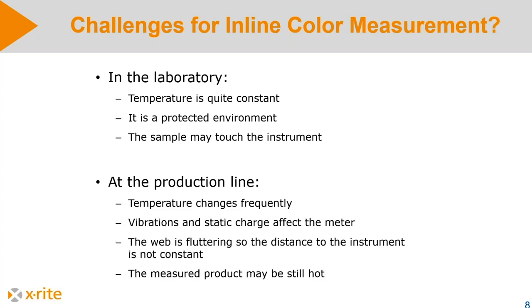If you look at the production system, the product at the production line, we have totally different conditions. When you start up the machine, the product is cold, the air is cold, then it's heating up quite quickly. During the day, if it's hot outside, you have different temperatures than in the night. So the temperatures are changing frequently, we have to take care of that. Temperature changes are, for all color measurement systems, the enemy; you have to calibrate frequently.